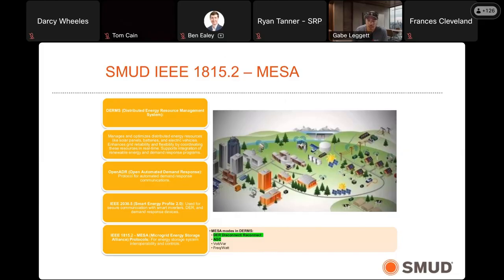1815.2, or MESA ESS, is really for front-of-the-meter generation or energy storage sources greater than 500 kilowatts. But we also support behind-the-meter communication protocols, like IEEE 2030.5 and OpenADR. We're looking at these three communication standards, and which one you need depends on whether the system is behind or front of the meter and the size of the system.